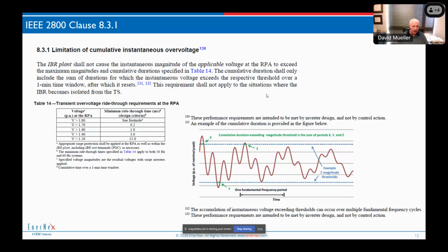Table 14 actually comes from the ride-through requirements of the plant. So on the one hand, we're saying we've got to ride through these voltages and not trip. But on the other hand, we're saying we can't cause voltages in excess of this. If you believe me, which is to say that the inverter manufacturers are going to try to comply with this by setting trip limits, then this kind of implies that they're going to set their trip limits identical to this table, because you can't both ride through and not trip without being right on the limit specified there. I think it's a little interesting.